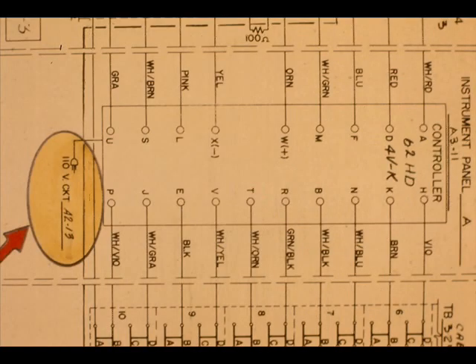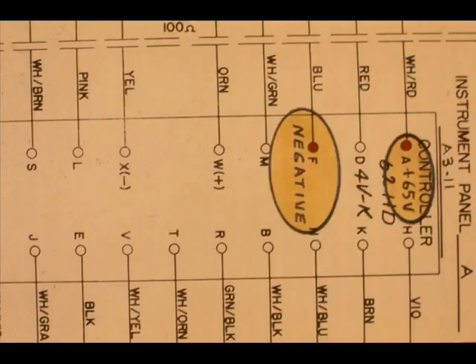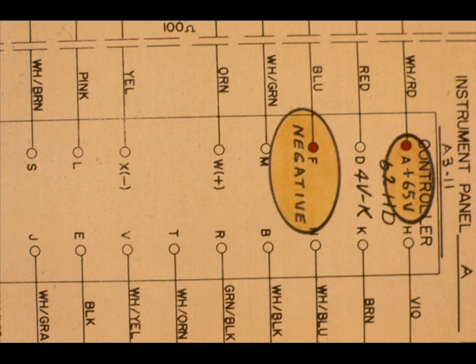This loop functions as follows. The controller receives 110 volts from AC circuit A213. The controller has a built-in power supply. Pin A is plus 65 volts. Pin F is negative.